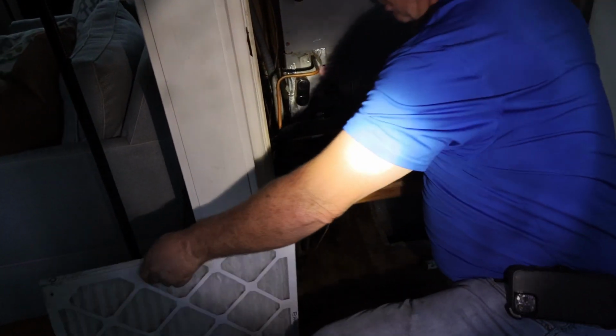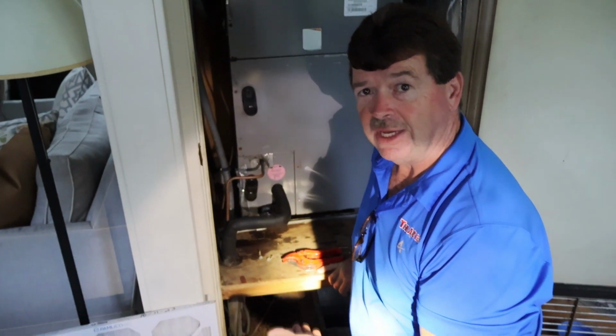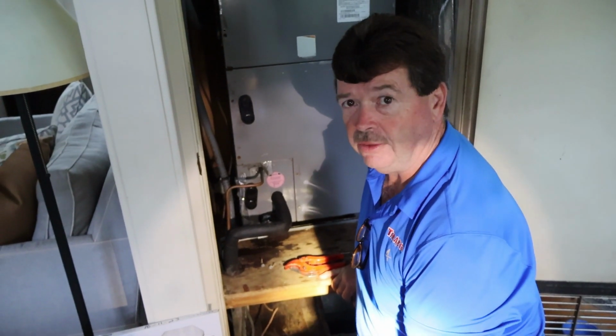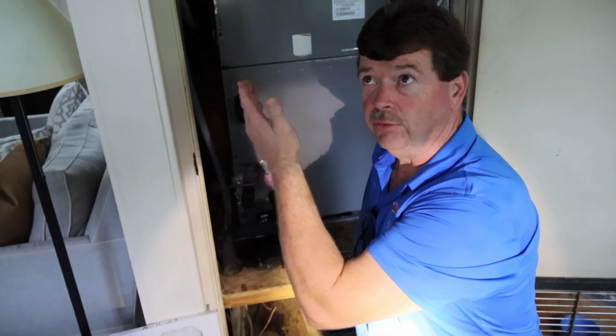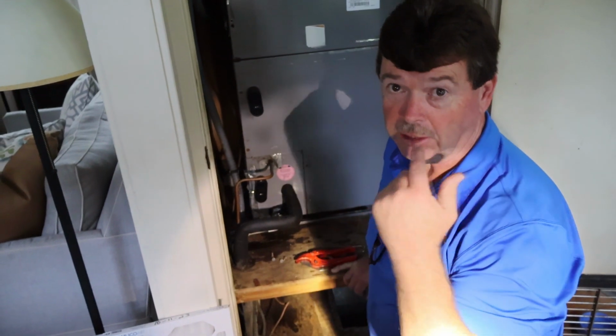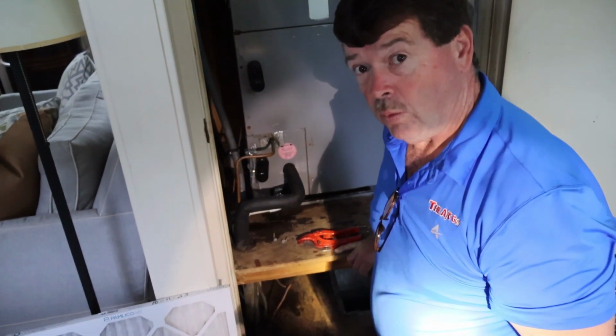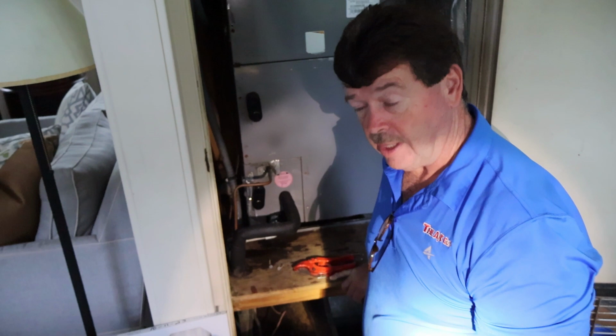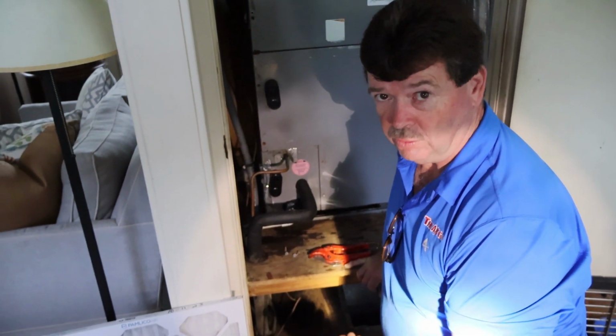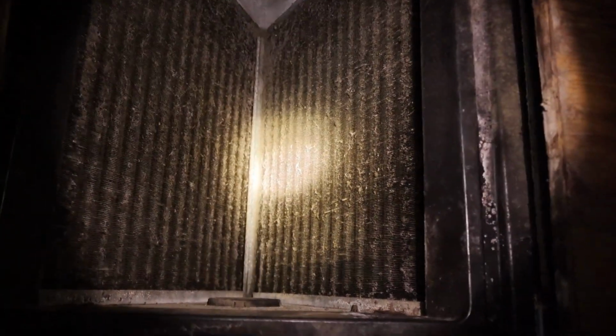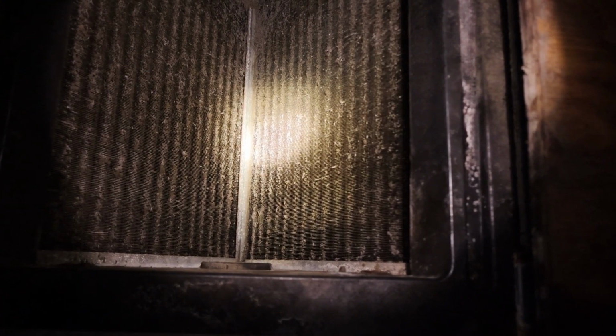Gonna zoom all out. Yep. We've removed the filter so we can take a look at the incoming side of the coil, and that's where the air goes into the coil, through the coil, and then through to the supply grills and supply duct system. We're going to take a good look at it. She's going to run the camera down and just see if the coil's dirty or not. Yeah, that's the coil right there. You can kind of see it. Yeah, you can tell the coil has some buildup on it. Probably does need to be cleaned.